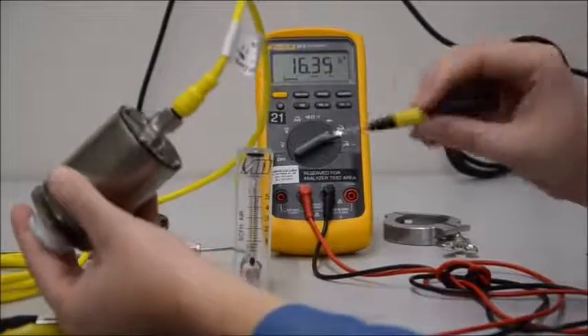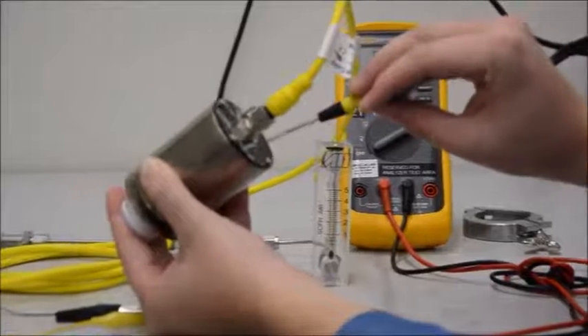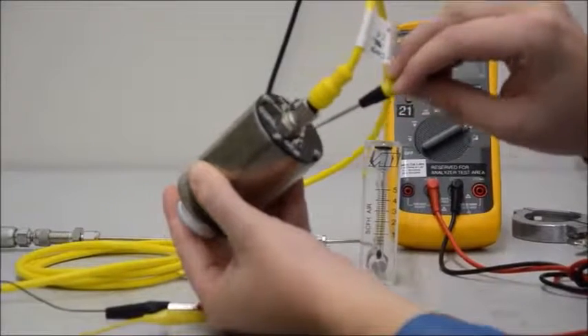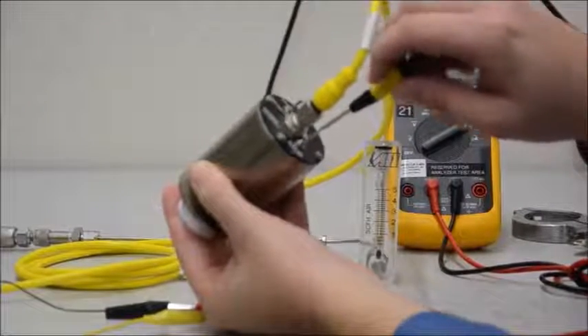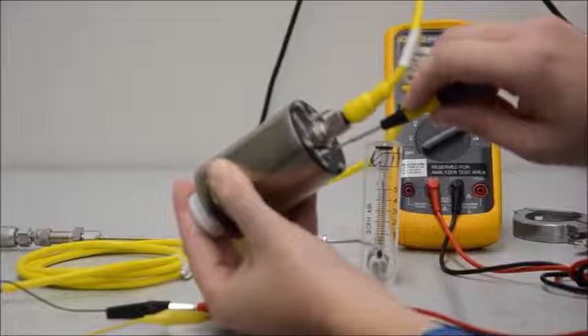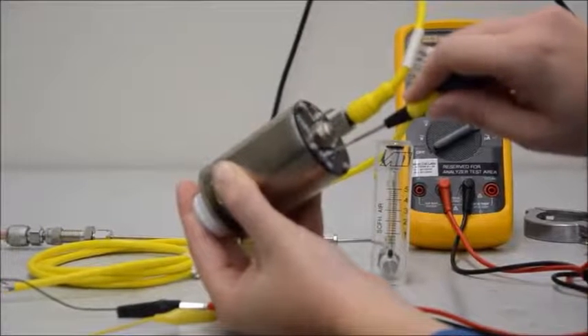Once settled, take a small flathead screwdriver and adjust the 4 to 20 potentiometer on the top of the analyzer until the multimeter reads 17.37 milliamps.